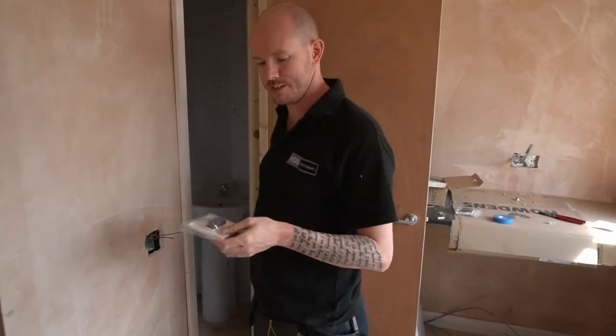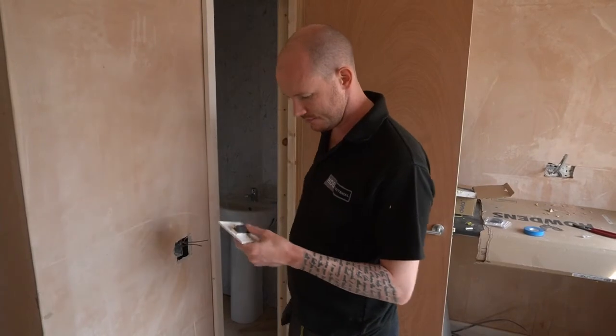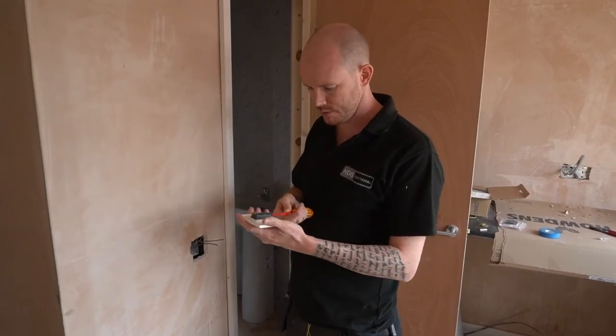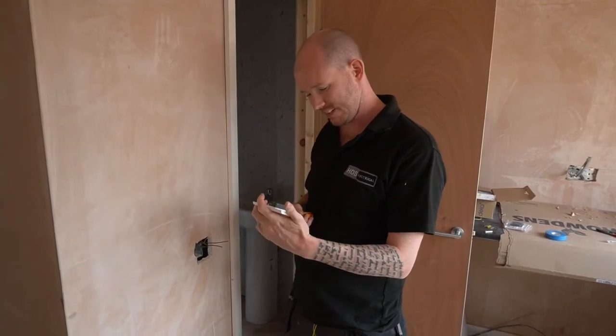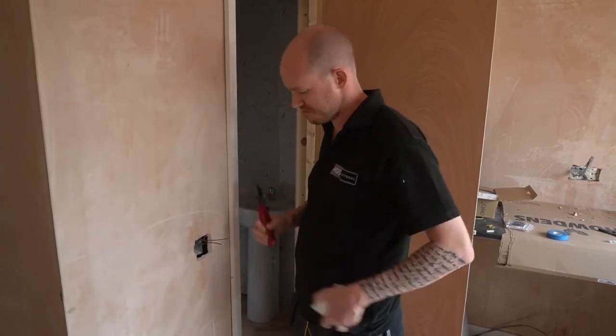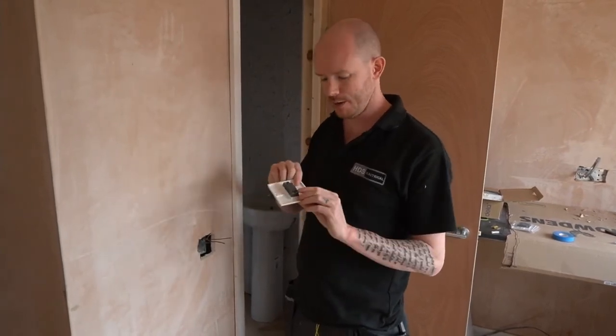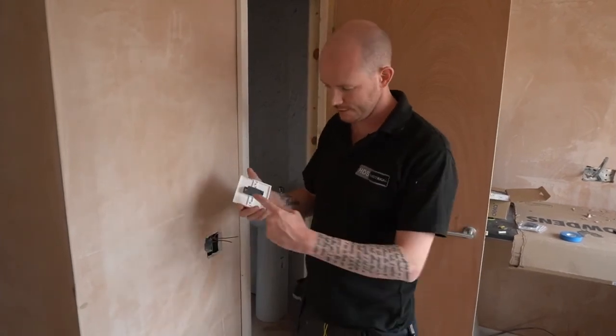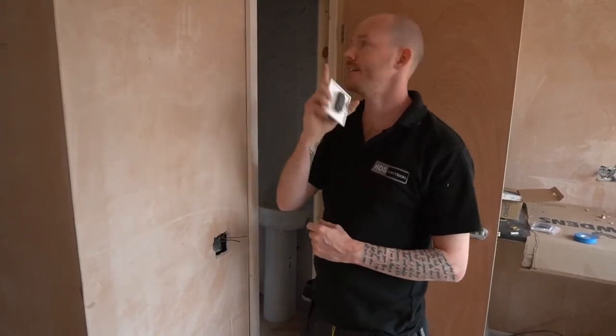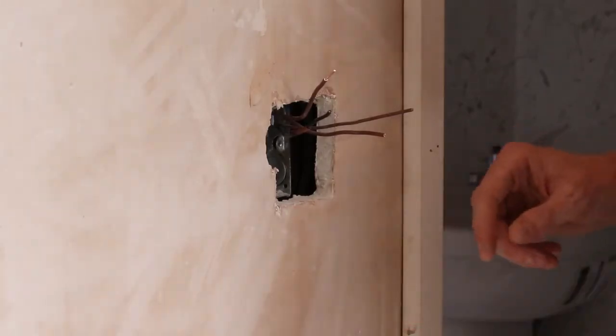I'm going to get my Deta switch — similar to the socket we did in another video, not a brand we usually use, but it feels quite nice. Not a brand I've ever fitted before but I can't say I dislike it. They've given us a one-way switch, and it's been so long since I've had one because we just fit two-way switches everywhere. So we've got common and L1 — permanent feeds going to common, our switch lines to the light and fan going to L1. Common on top, L1 at the bottom.